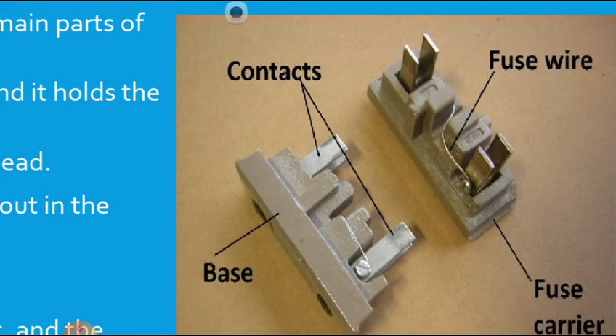Whenever an arc appears, we need to extinguish it using different media. But in the KitKat fuse we do not provide any media to quench the arc. So the sparks may fall on nearby devices on the ground. If this type of fuse is used in chemical, gas or cotton industries, there is a risk of fire accidents. So these are the disadvantages.